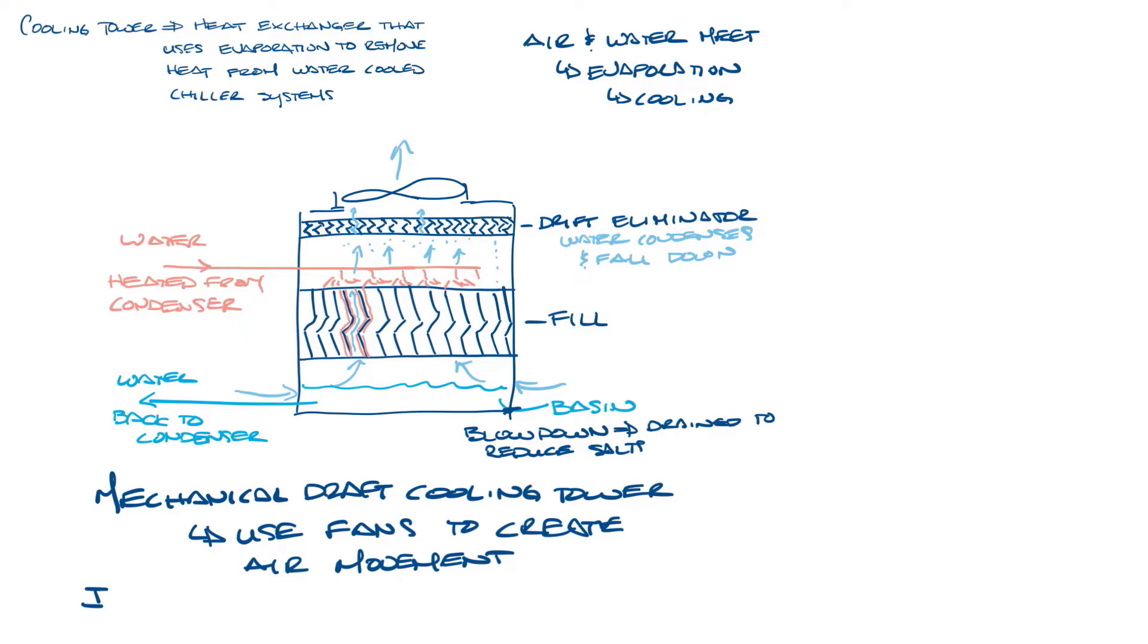Induced draft cooling towers have a fan that's located at the top of the cooling tower pulling the air through the tower. Forced draft cooling towers have a fan located at the bottom pushing the air into the tower. So you can see with the fan on top of my drawing it's an induced draft tower.